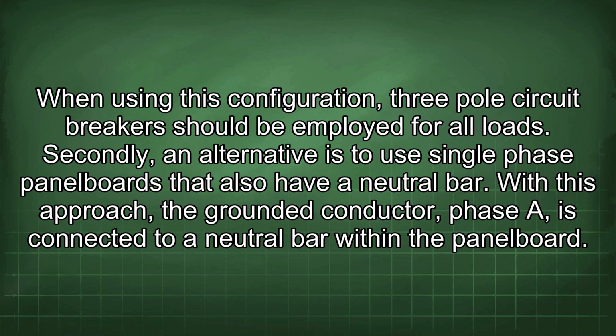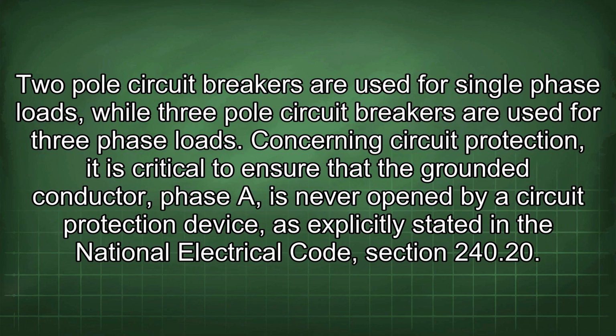Secondly, an alternative is to use single-phase panel boards that also have a neutral bar. With this approach, the grounded conductor, phase A, is connected to a neutral bar within the panel board. 2-pole circuit breakers are used for single-phase loads, while 3-pole circuit breakers are used for 3-phase loads.